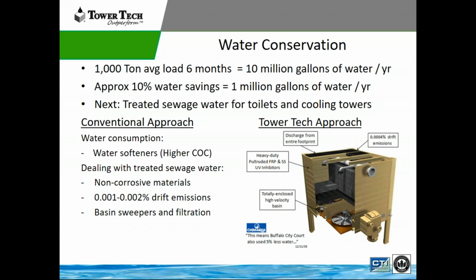You'll notice on a traditional tower, it goes through a high velocity point where the fan is on the top of the cooling tower. It's a higher velocity than the velocity that we're discharging off the top of the cooling tower. It is a lot larger surface. Because of that, we have 0.0004 drift emissions on ours versus the traditional tower of 0.001 or 0.002 drift emissions.